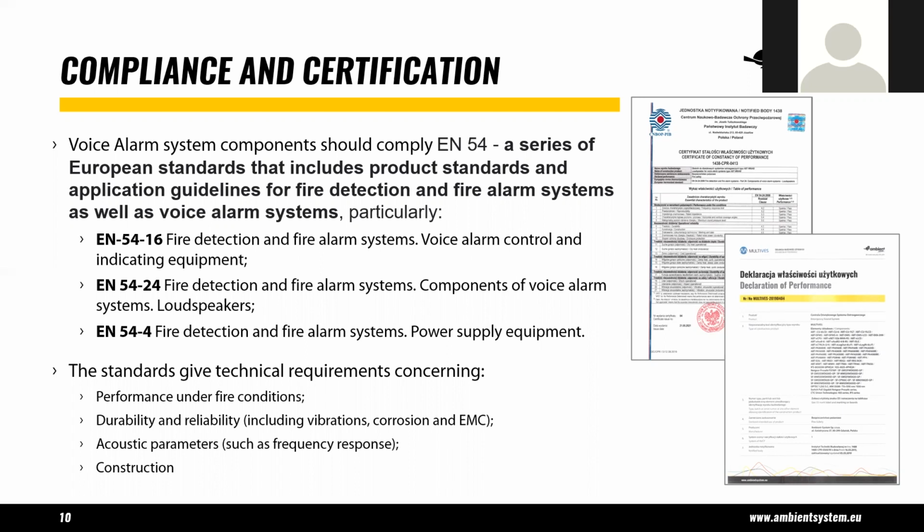So the EN standards, I mean, we're complying to parts 4, 16 and 24, but there's 30 odd parts, and the voice alarm system falls as a small proportion of the overall fire alarm standards. But the fundamental purpose of these EN 54 standards is that a product that you put on the market is not self-certified by you to say that it will achieve the reliability criteria, it will perform under fire conditions, it's properly constructed.